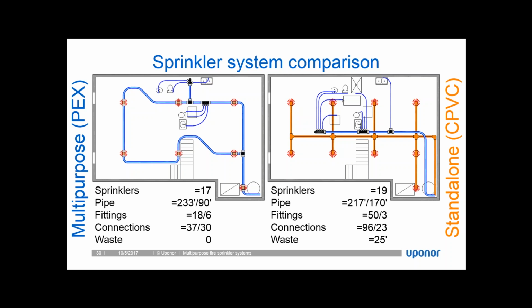And then we're still looking at that same amount of waste. We didn't add any more waste for the plumbing system because, again, we're using Uponor PEX tubing. We're just going to cut it out of the coil, and whatever we don't use, we bring to the next job site. So this is the overall comparison from a PEX system to a standalone system when we're using pendant sprinklers everywhere.